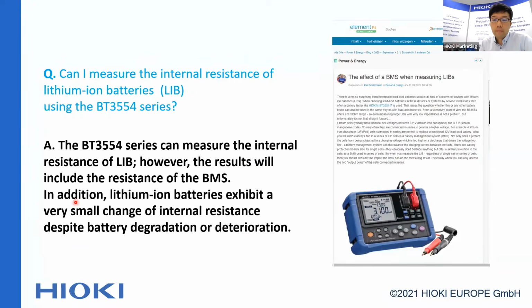That's a good question. In principle, the BT3554 series can measure the internal resistance of LIB. However, the result will include the resistance of the BMS, which is normally attached to the LIBs to control charge and discharge for safety reasons. In addition, lithium-ion batteries exhibit very small changes in internal resistance despite battery deterioration, meaning it's difficult to find deteriorated LIBs using this battery tester. At least you can probably find that a cell is faulty if its resistance is clearly different from the other cells. So for maintenance purposes, the BT3554 is not the best solution for LIB UPS at the moment.